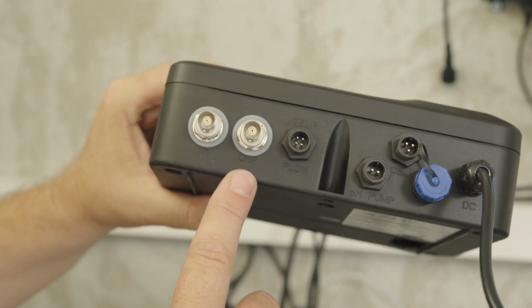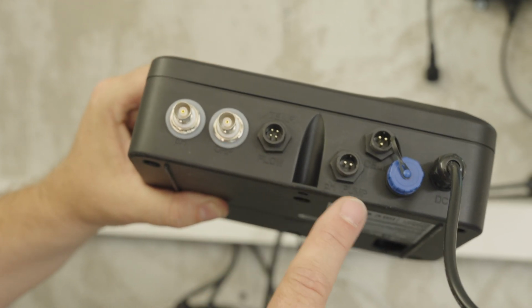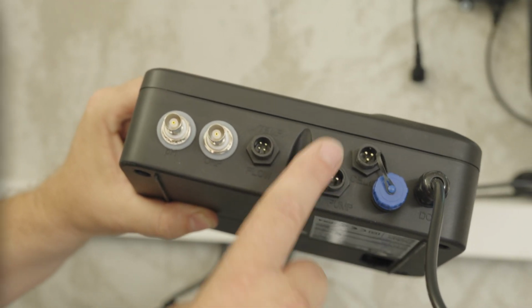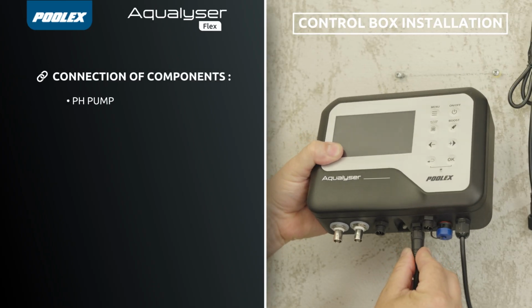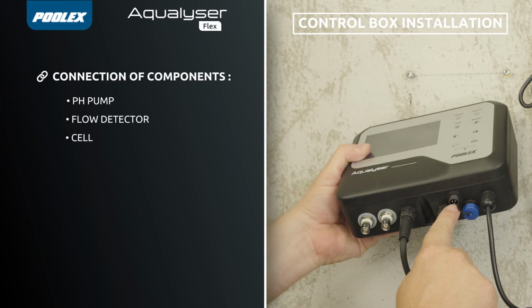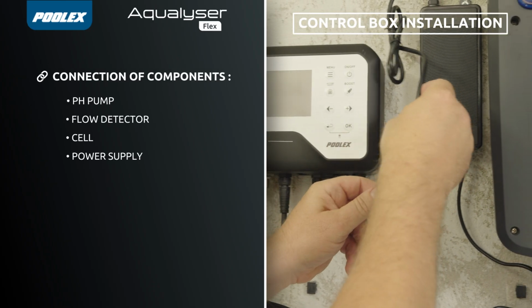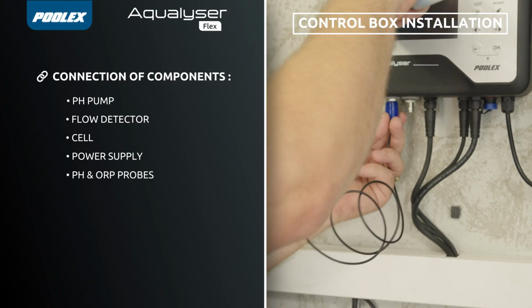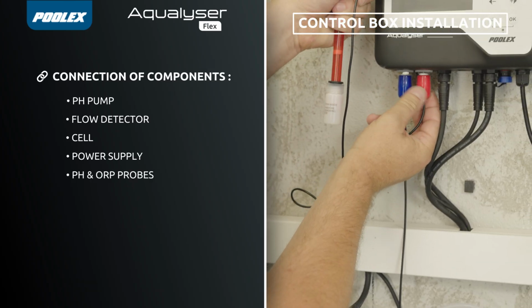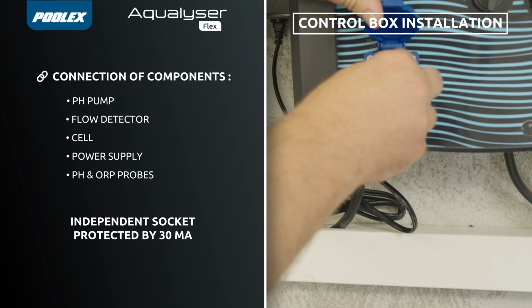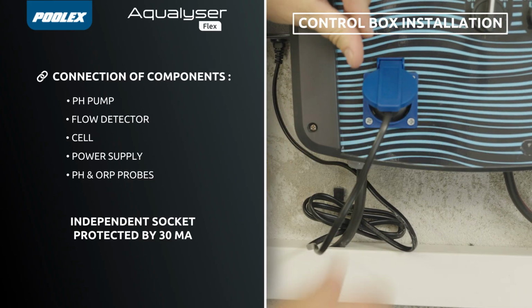Connect each component to the flex box. To help you, we have integrated a notch guide on each connector. Connect the pH pump, the flow detector, the cell, the power supply to the transformer, then the probes, blue pH probe and red ORP probe. Plug the box into a socket protected by a 30 mA circuit breaker.